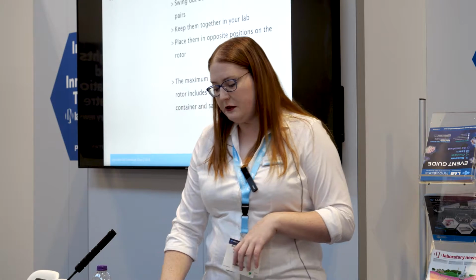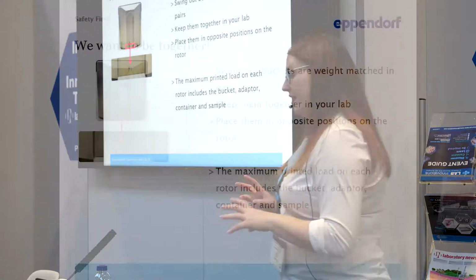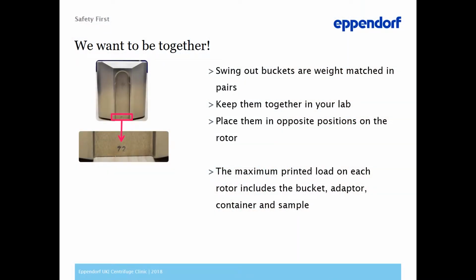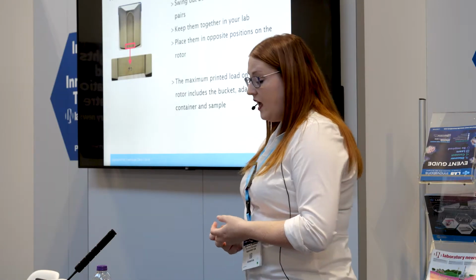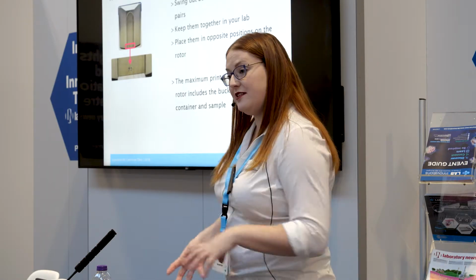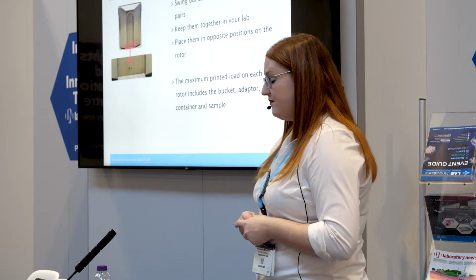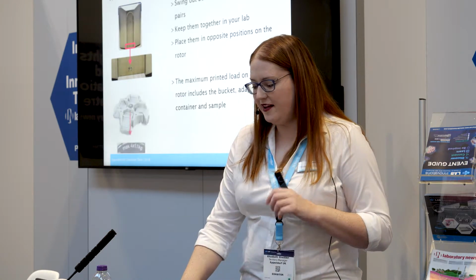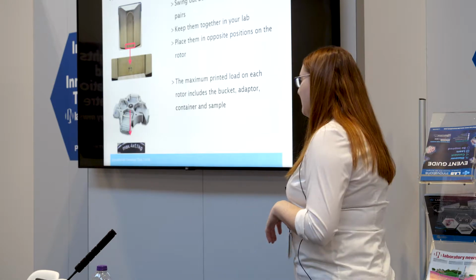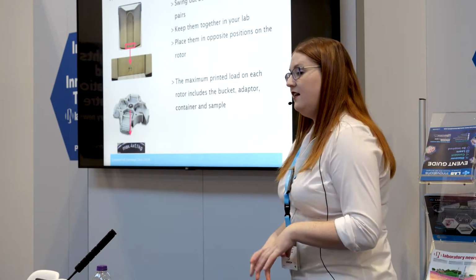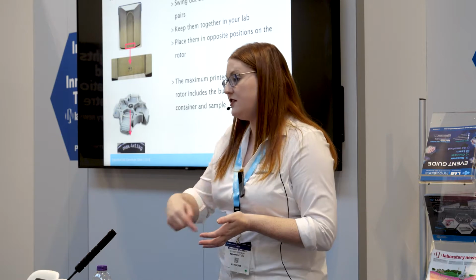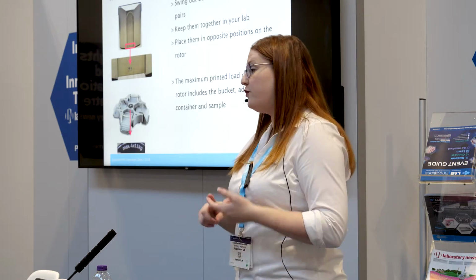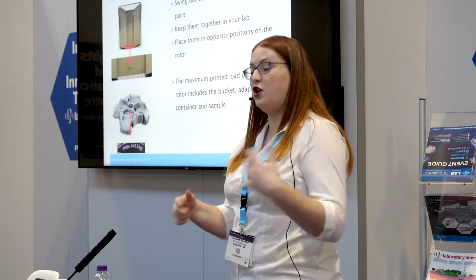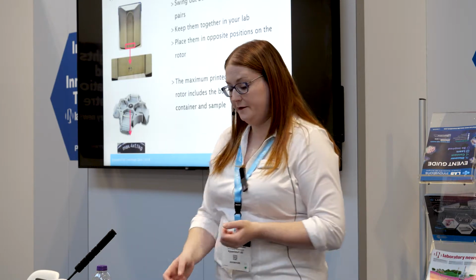So, swing out buckets are actually made in pairs so that they are perfectly matched to each other. Most people think all buckets are the same, but they are definitely made in pairs. And so when you get a new centrifuge, try and keep them together, which almost never happens. And also, the maximum load for a swing out rotor is printed on it. It's also on the fixed angle rotors. It's in the middle. It will tell you that includes the weight of the rotor and the buckets and any adapters on top of your samples. Okay?